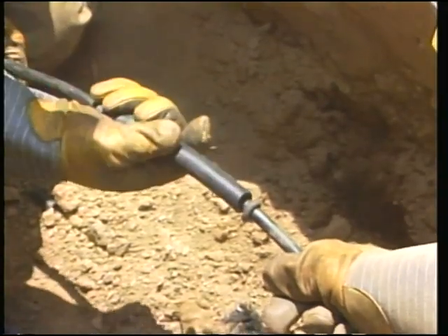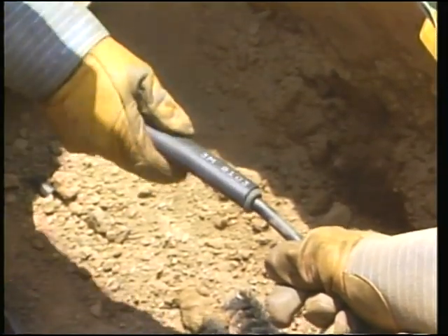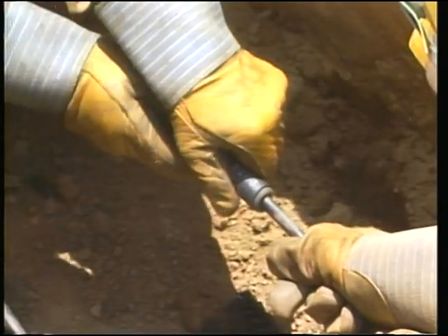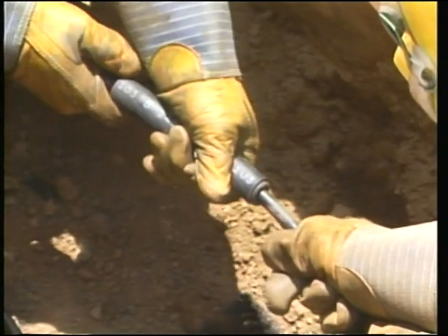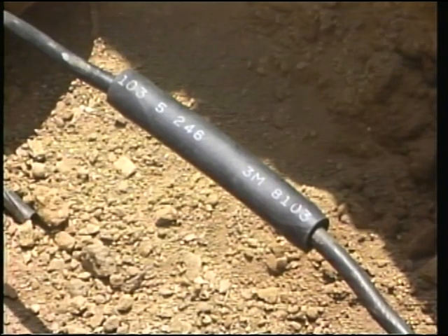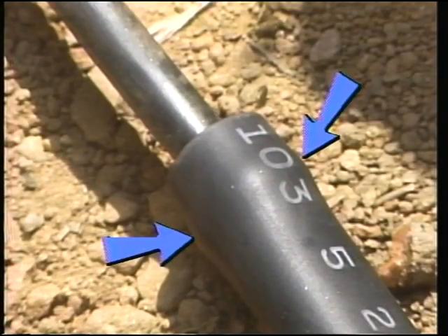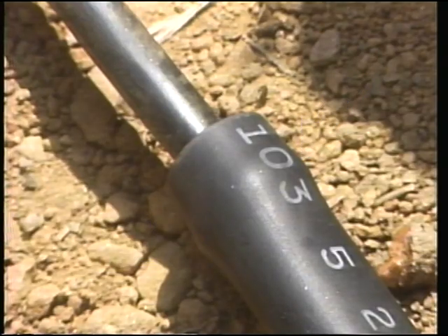When the compressions are complete, the insulating tube and the O-ring are rolled over the conductor splice and over the O-ring on the other cable. In the tube's final position, the O-rings will be on the cable insulation and under the insulating tube, making a watertight seal over the conductor splice.